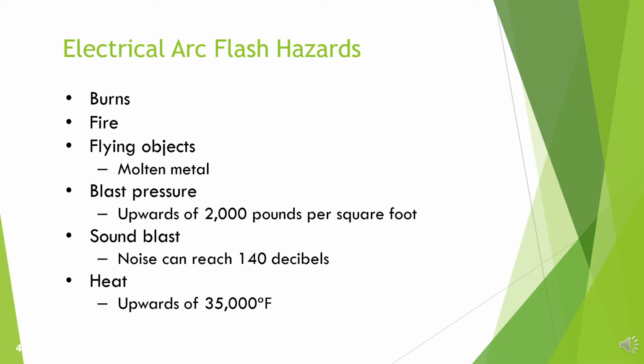Next is fire. Arc flashes can help ignite a fire. So if you have any kind of ignition source around you when an arc flash is present, you will be introducing a fire hazard at that point, just making the situation that much worse. Next is flying objects such as molten metal. These will be produced not so much by the arc flash, but by the arc blast, the actual circuit blowing up. Blast pressures can be upwards of 2,000 pounds per square foot.